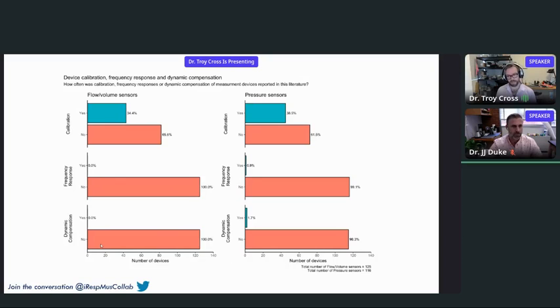There could be a number of reasons for this. The most likely one is that flow sensors, typically the pneumotachographs that are manufactured and commercially available, there's generally an understanding, I guess, that their frequency response is adequate. And so I think we don't feel compelled to report on it. But I think where it is more important, and less observed, is the impact of frequency response, calibration and compensation on our pressure sensors. So let's have a look at the pressure sensors now.